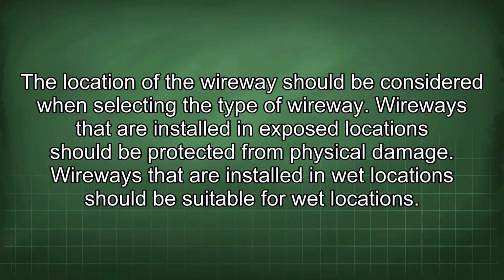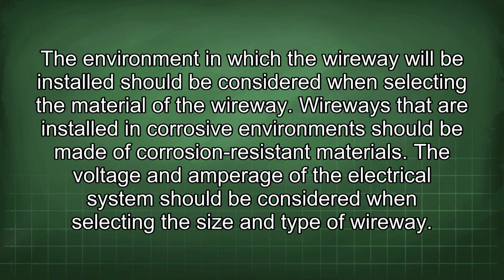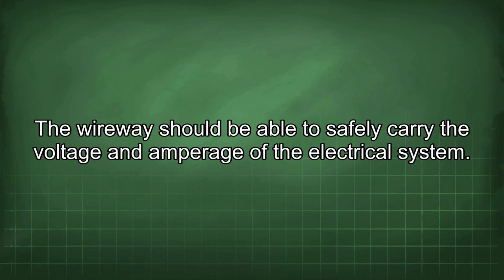The location of the wireway should be considered when selecting the type of wireway. Wireways that are installed in exposed locations should be protected from physical damage. Wireways that are installed in wet locations should be suitable for wet locations. The environment in which the wireway will be installed should be considered when selecting the material of the wireway. Wireways that are installed in corrosive environments should be made of corrosion-resistant materials. The voltage and amperage of the electrical system should be considered when selecting the size and type of wireway. The wireway should be able to safely carry the voltage and amperage of the electrical system.